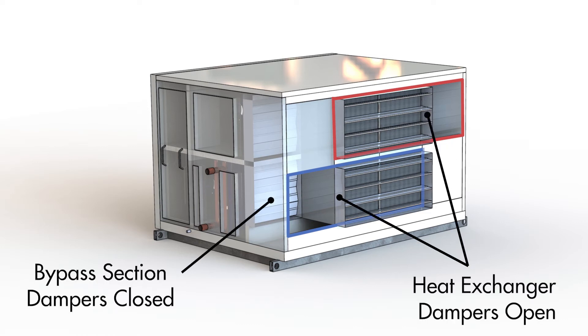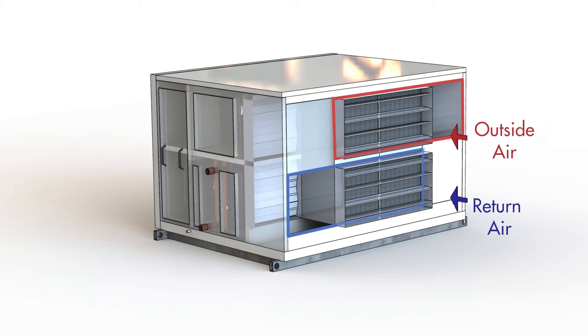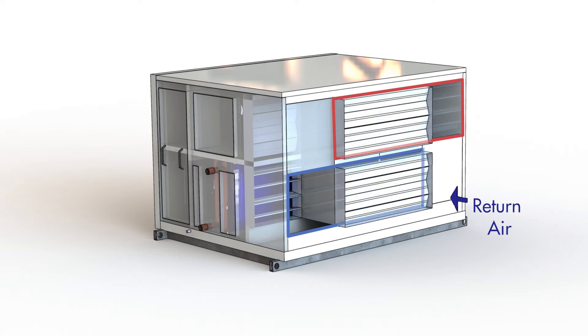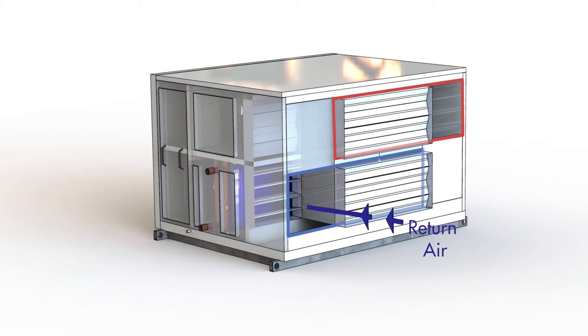In heat or energy recovery mode, the heat exchanger dampers are open, while the bypass section dampers are closed. This forces the outside air and the return air from the space to pass through the air-to-air heat exchanger. But in scenarios where there is no outside air required, the heat exchanger dampers close and the return air bypass dampers open. This forces the return air to bypass the air-to-air heat exchanger and flow back into the indoor space.